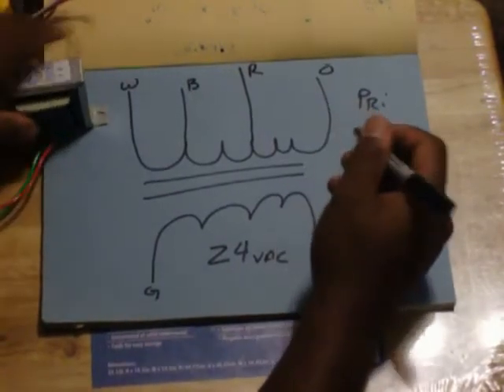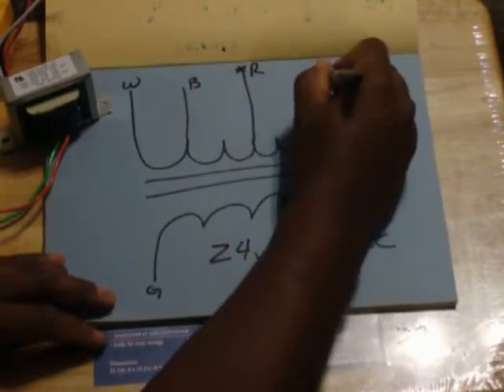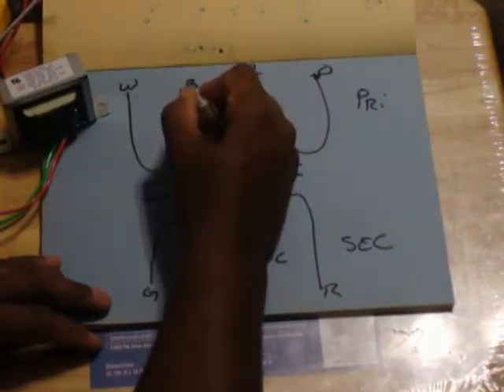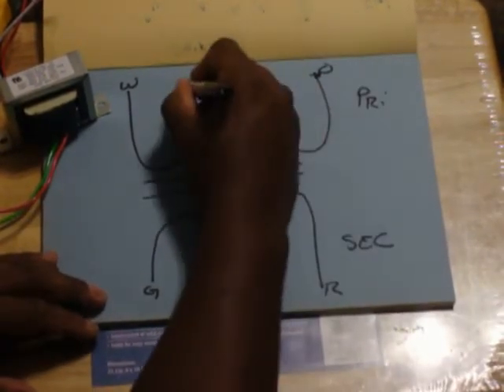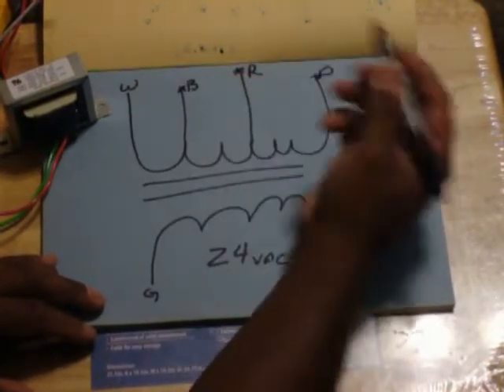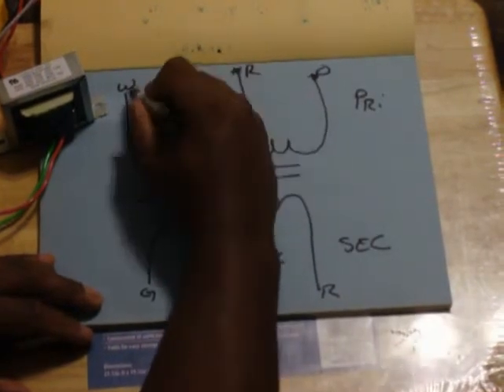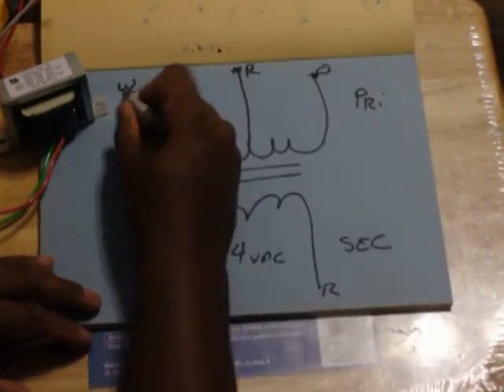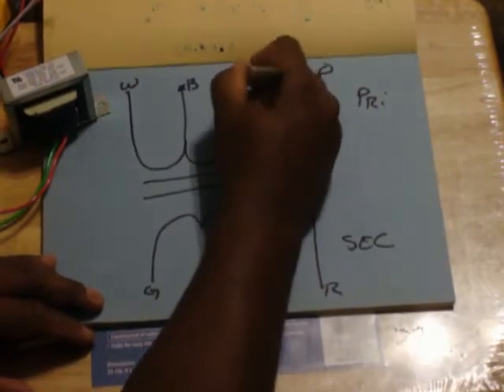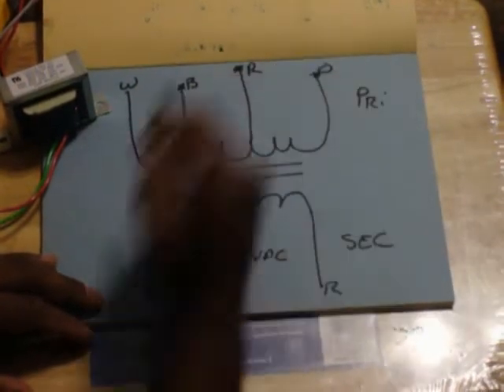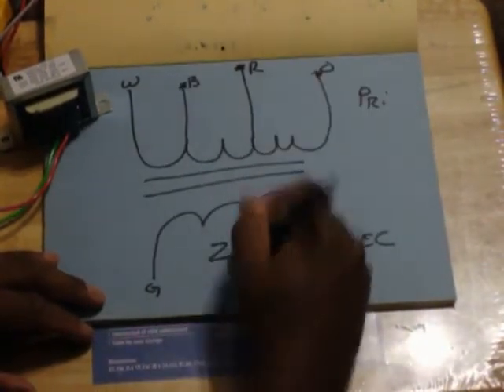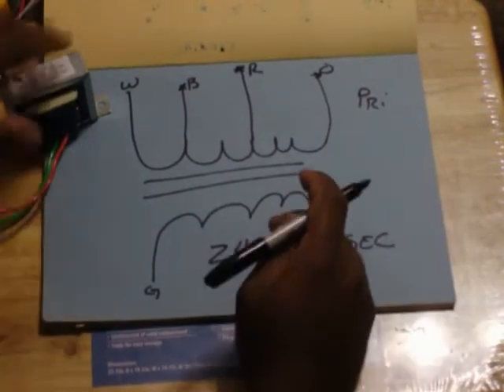Okay? If you wanted to hook this system up to 110 volts, you cap off your orange and your red, and you hook up your 110 between white and black. If you want to use 208, you cap off your black and your orange, hook up white and red. If it was 230, cap off red and black, hook up white and orange. So no matter what, you're going to use white. Whatever you don't use, you cap them off. Do not hook them together. Cap them off. If you hook them together, you're going to short it out. But no matter what voltage you hook up, you're always going to come out with 24 volts.